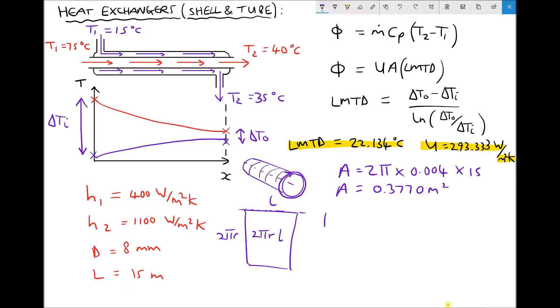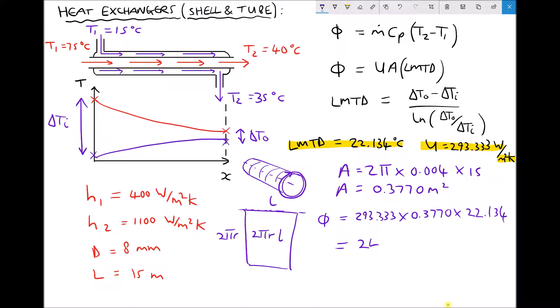Finally, the rate of heat transfer equals U times A times LMTD: 293.333 times 0.3770 times 22.134, giving a rate of heat transfer equal to 2448 watts, or 2.448 kilowatts.